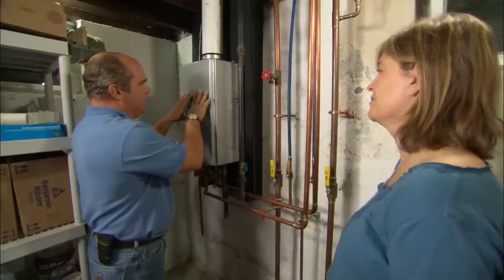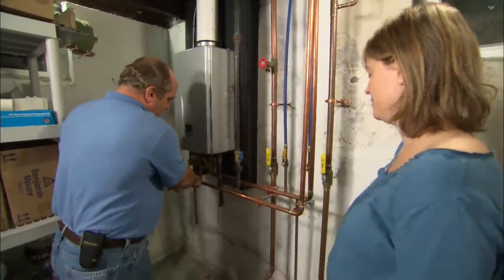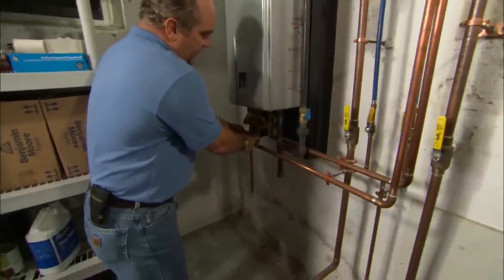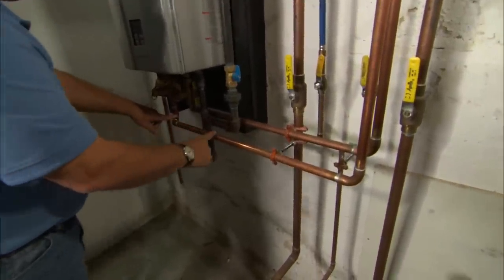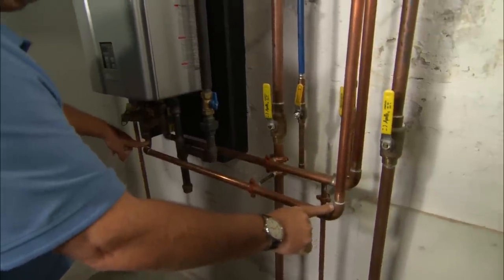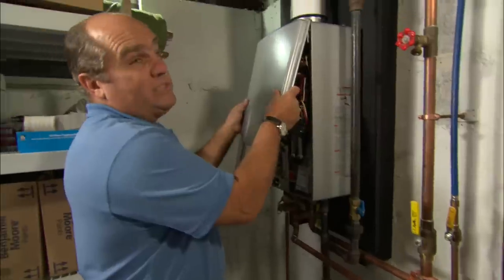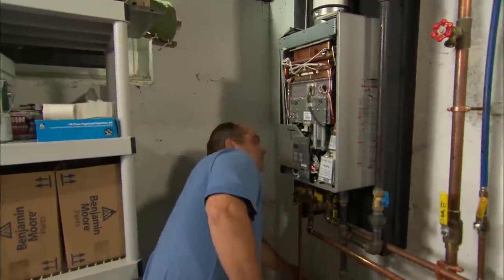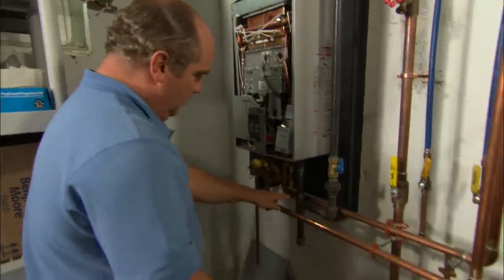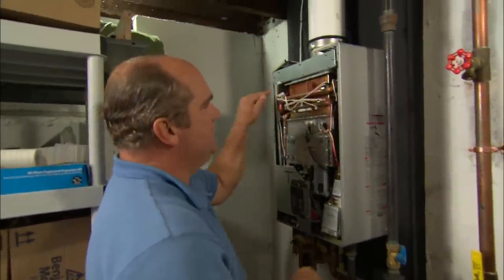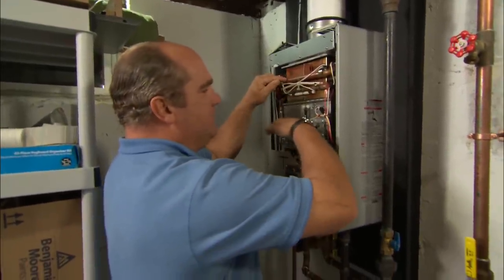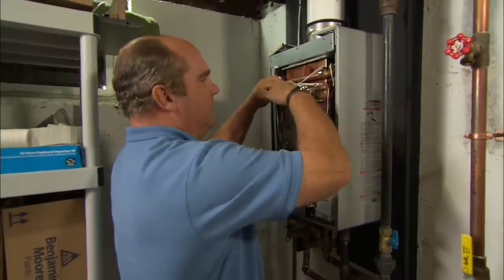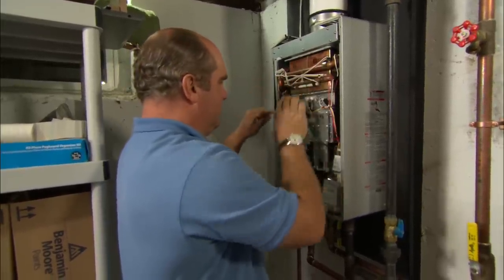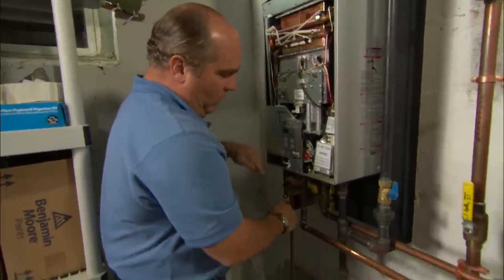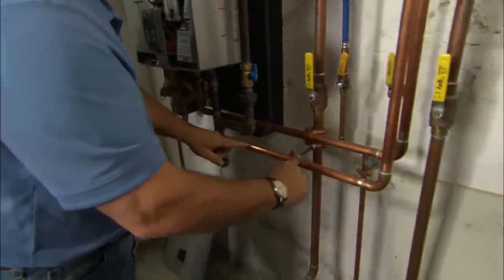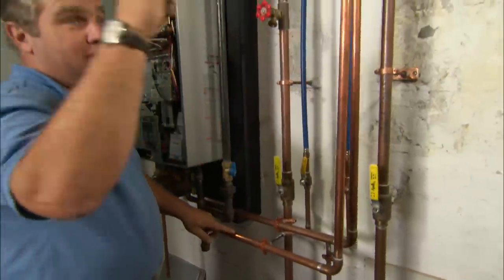It turns off and gets ice cold. That means this pipe, the hot water pipe, from here up to the faucet upstairs gets cold because the basement's cold. Now when you open up the faucet upstairs and want hot water, here's what happens: cold water comes in here, goes up through this heat exchanger, with a burner right underneath. The burner comes on, has to heat the water in the heat exchanger, and has to empty out all this cold water in the pipe through the faucet before you feel any hot water upstairs.